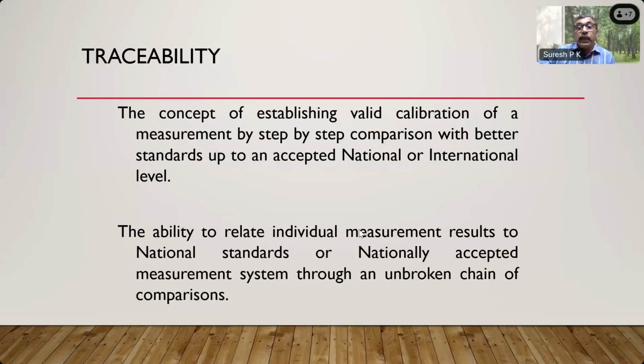Now, there is a concept called traceability. What is traceability? The concept of establishing a valid calibration of a measurement by step-by-step comparison with better standards up to an accepted national or international level is called traceability. The ability to relate individual measurement results to national standards or a nationally accepted measurement system through an unbroken chain of comparisons. Unbroken chain of comparison is very important.